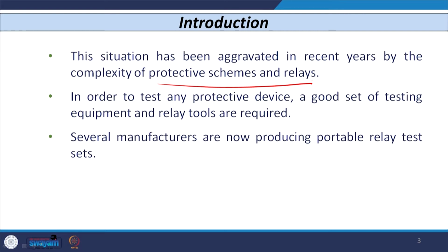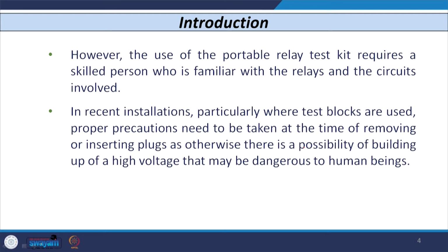In order to test any protective device, a good set of testing equipment and some tools are required. Several manufacturers are now producing this type of tool through which we can carry out the testing of relays. Such tools are manufactured by, maybe, Alstom. The other manufacturer is Omicron. There are some other manufacturers also who provide such relay testing equipment. However, the use of a portable relay test kit requires a skilled person, because whenever we use such a kit, we need to take some precautions, and we need to disable several contacts and enable several contacts if we wish to carry out a certain test. So, this needs a very skilled person who has knowledge of the relay as well as of the portable relay test kit.